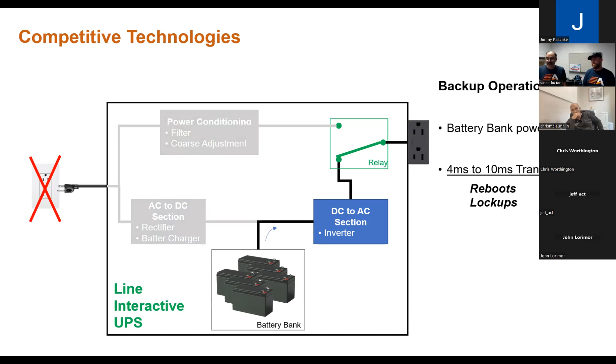So this is a graphic I put together. This is the output that we've seen on many line interactive UPSs. Reading from left to right, you get your sine wave, the sine wave you're getting from the power company that is passing through the unit. You can see right there at that point where the power goes out, now you've got 0 volts, for 4 milliseconds, I drew it there.